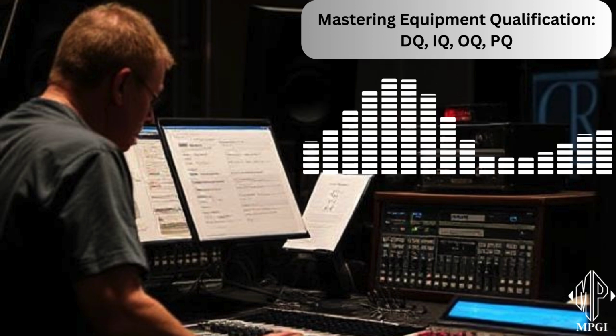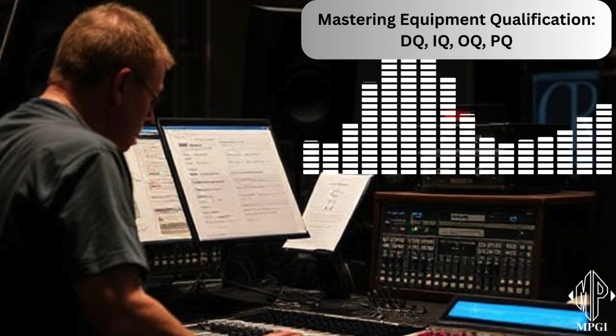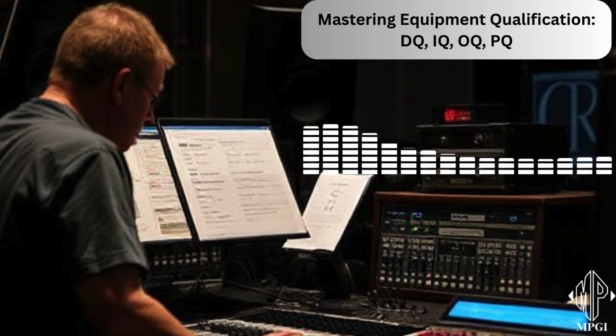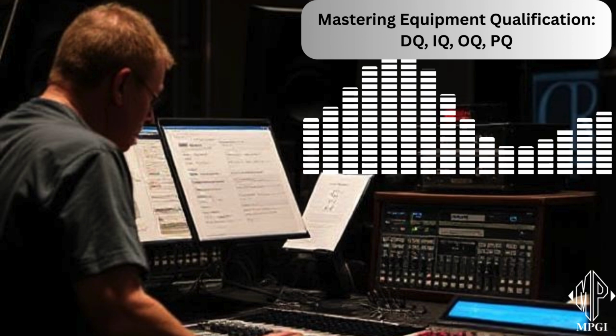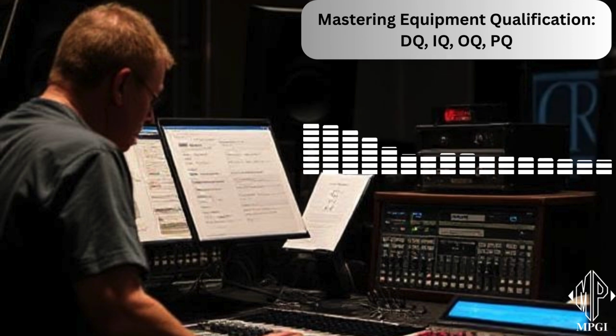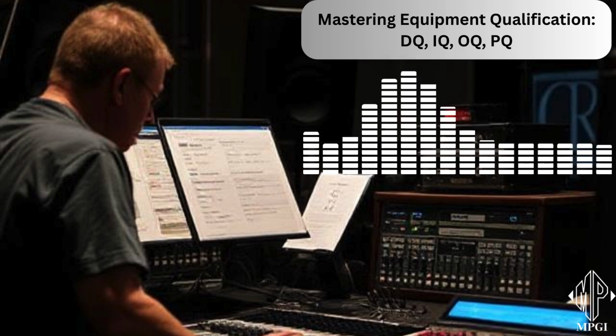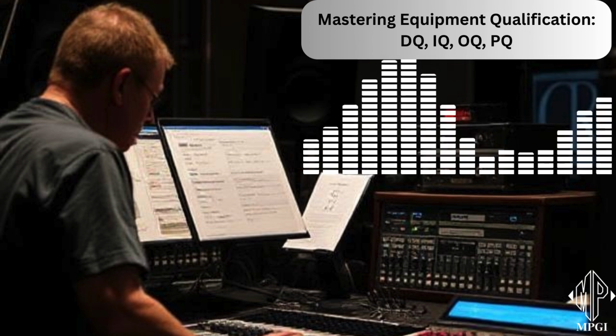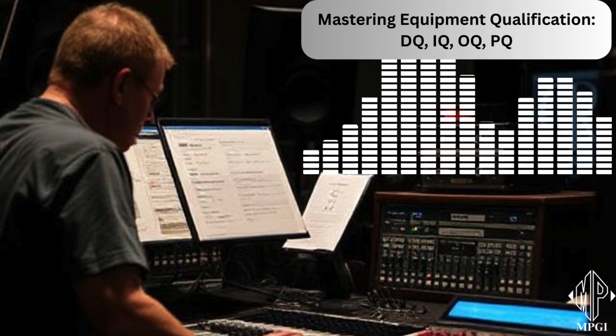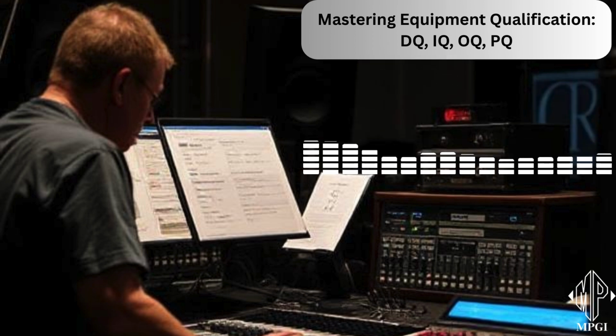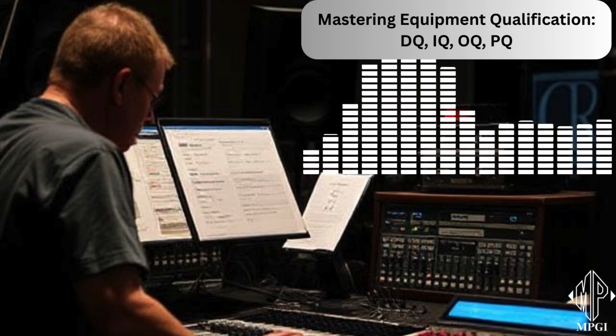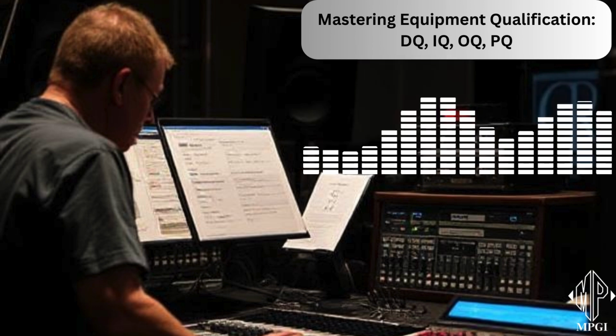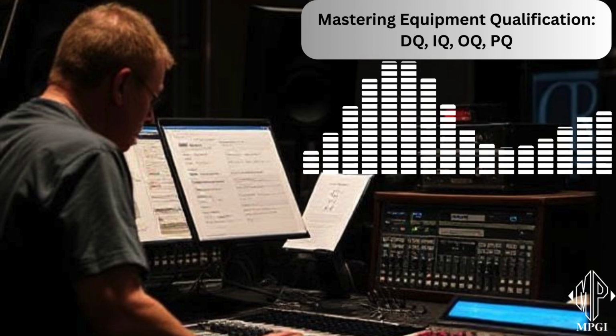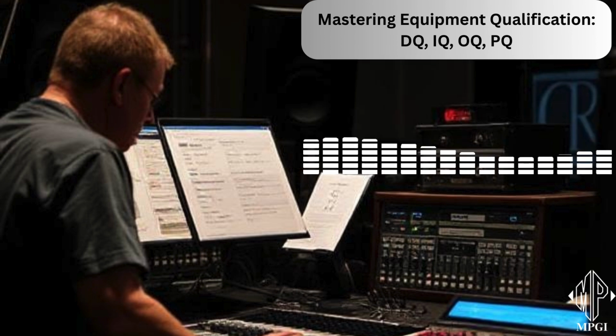Thorough training is essential. So what kind of documentation comes out of the IQ process? Well, you've got the IQ protocol itself, the equipment specifications and manuals, calibration certificates for any equipment used, and installation checklists detailing the checks performed. They're not messing around with that documentation, are they? Nope. You've also got test and verification records documenting the results of every check. So it's all there in black and white. Right. And finally, the final IQ report summarizes everything and provides a conclusion on whether the installation was successful. A comprehensive record of the entire process.